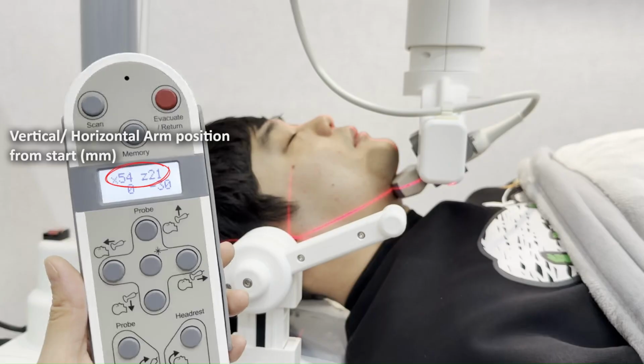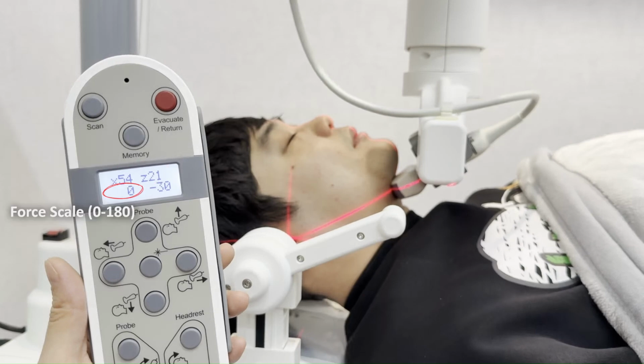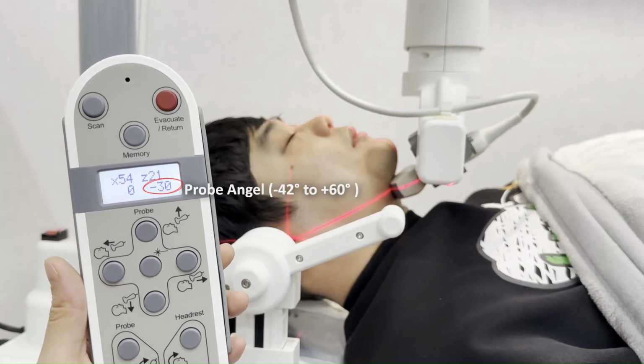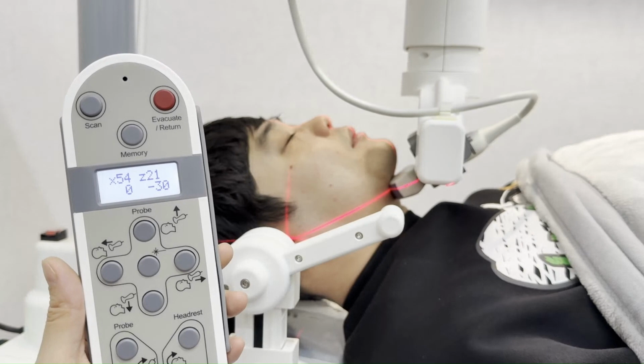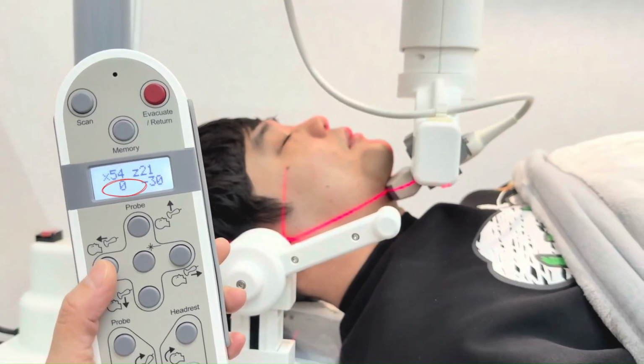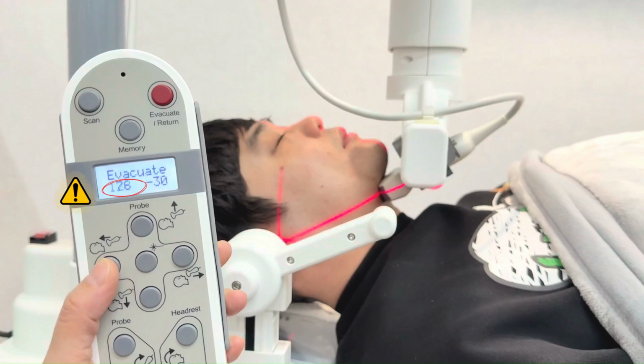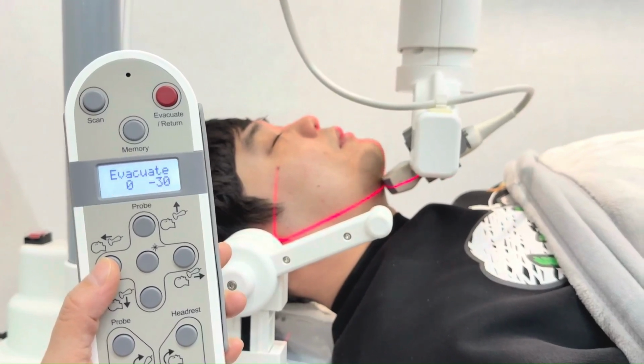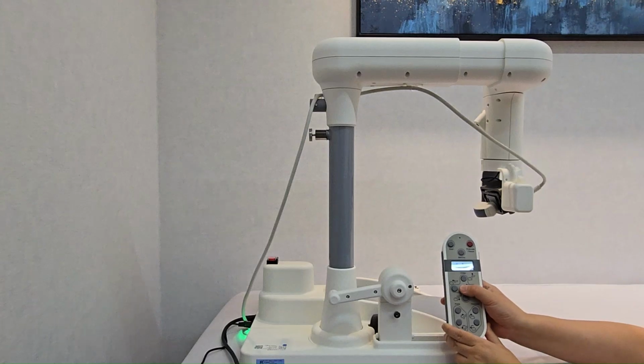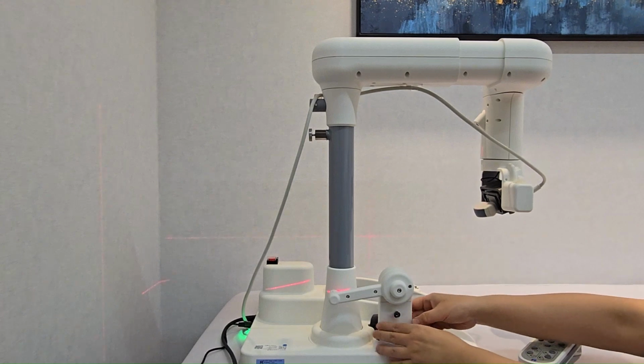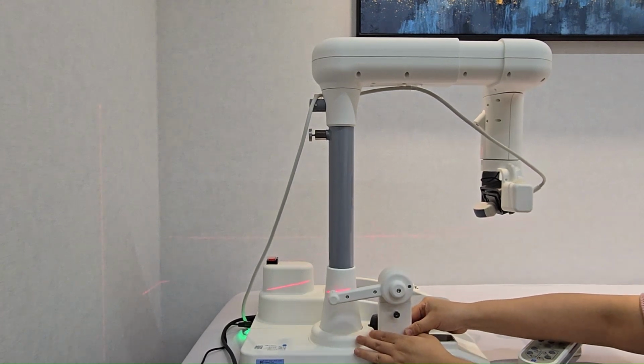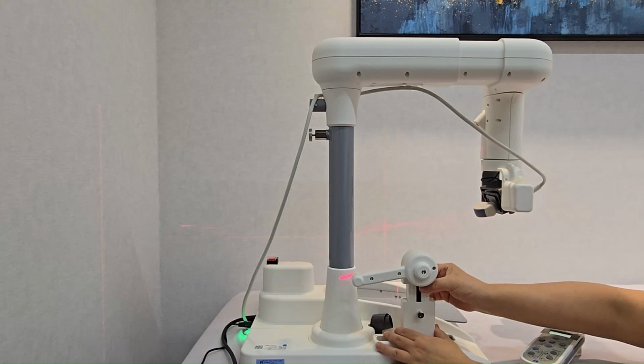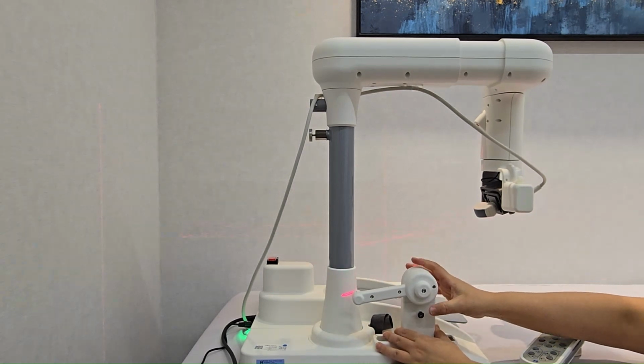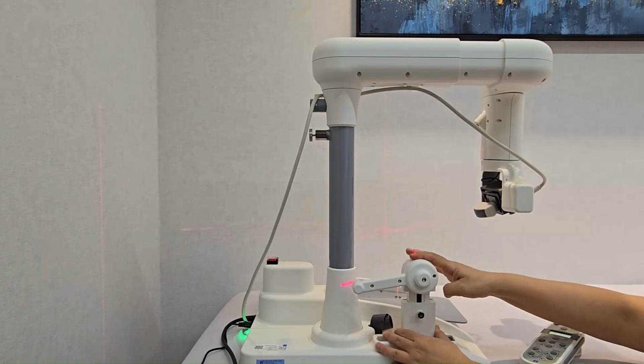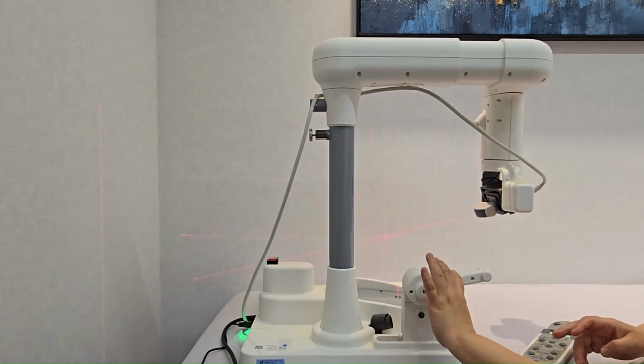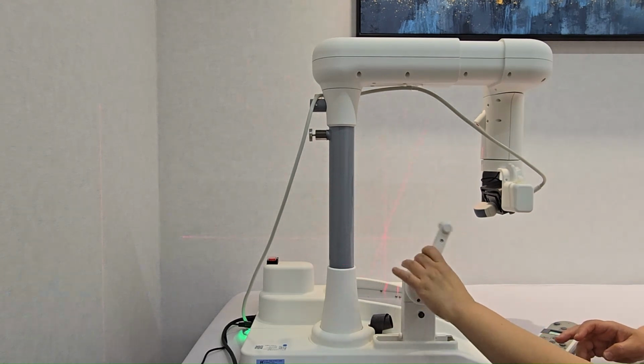The display shows real-time values for arm position, force scale, probe angle range, and head support status. A force above 180 triggers evacuation. Near zero is best for initial contact. The laser module on and off button is in the center of the hand controller. To adjust the laser module position, manually slide it left or right, lift it up, or push it down to the desired location. The module handle can also rotate 180 degrees in either direction for proper alignment.